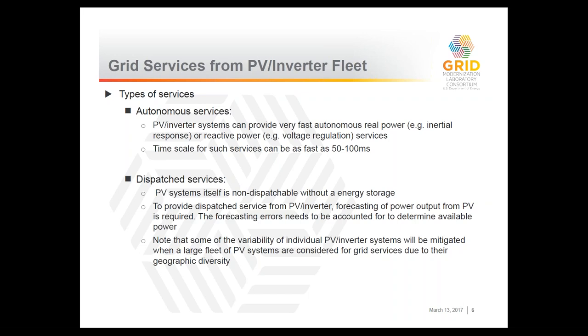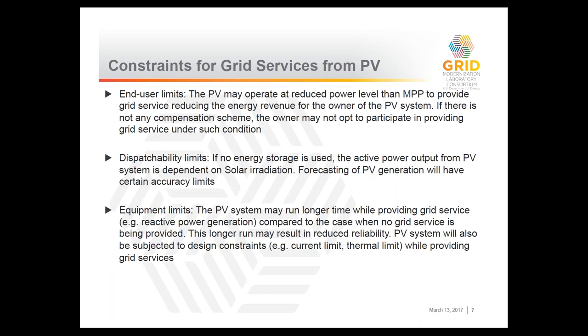Now, note that some of the variability of individual PV inverters will be mitigated because of this large fleet, as I mentioned earlier. This seems a little bit new, but there are some efforts going on. There was an enrolled project where we are working with Puerto Rico, and we are utilizing a big PV inverter fleet to support the voltage or frequency regulation of their whole system. So it can be done, but we obviously need something such as forecasting to make it a dispatchable service.